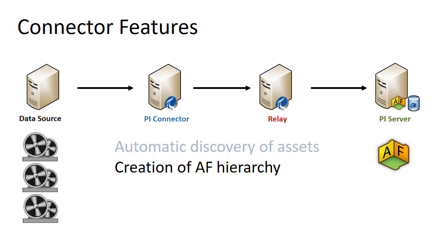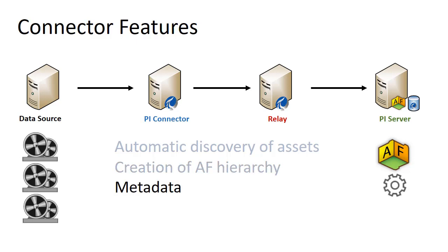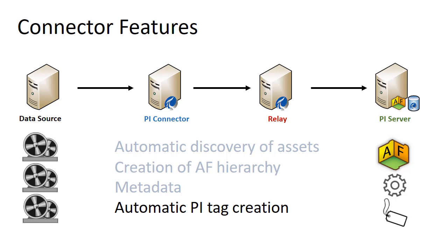In addition to the creation of the hierarchy in your database, attributes will be created containing metadata and PI point data references, all with fully configured tags on your PI data archive. There is no longer a need to manually create PI tags, greatly reducing the amount of manual configuration required when using connectors.